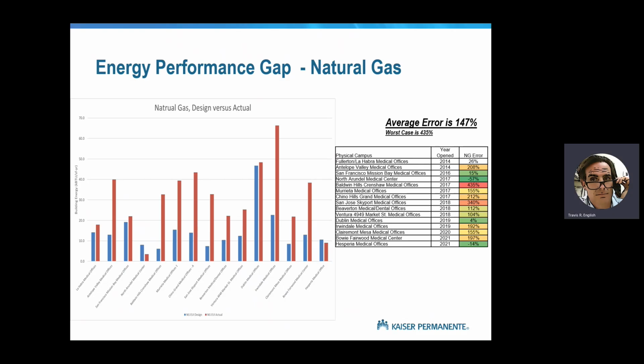So it's not at all uncommon for us to open a building and to see natural gas in the first couple of months that's off by a factor of 2 or 3 times the model. So let's get into this. And before we dive too deep here, let me mention that for domestic water heating, the next 5 slides I'm going to show you are BTU per square foot numbers. But somebody in the room would raise their hand and say, hey, domestic water heating is part of the natural gas number. Yeah, that's true. But the most conservative estimates you'll find for domestic water use are 0.5 BTU per square foot to 1 BTU per square foot during the occupied hours. So bear that in mind. In most cases, it's actually a negligible number to the overall count.